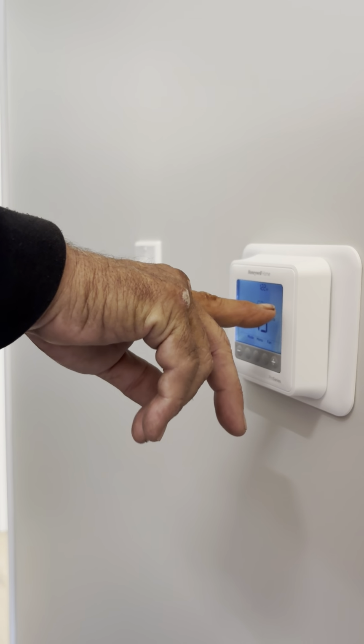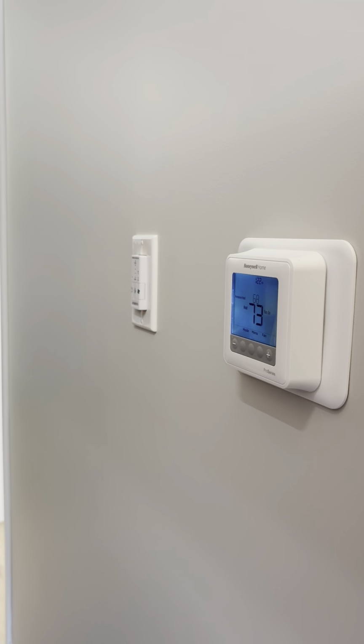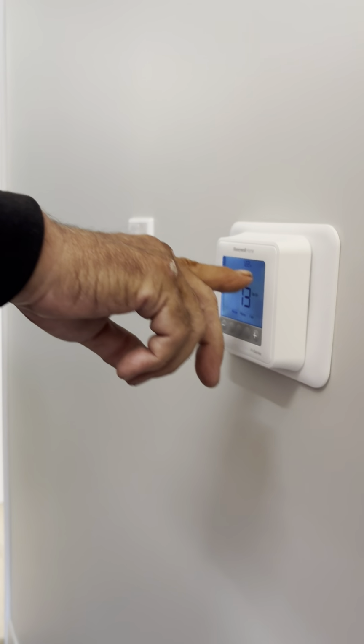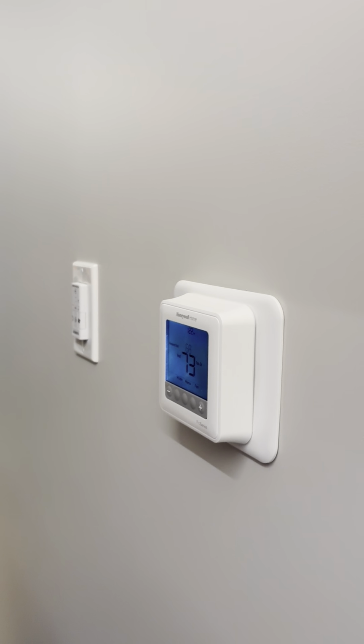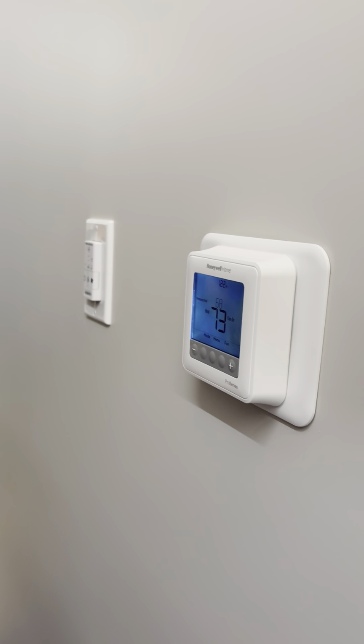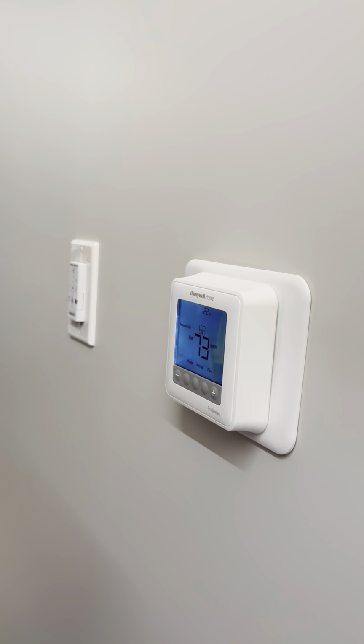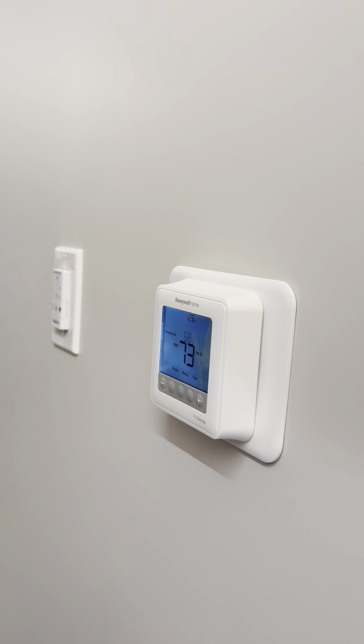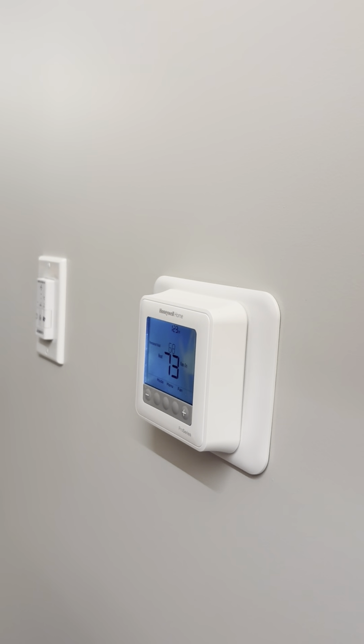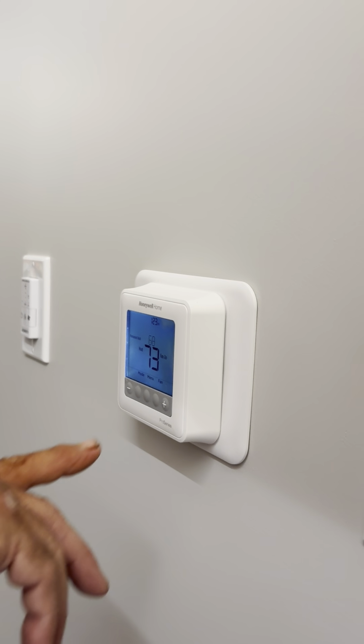Once it's flashing, like it is right now in the corner, it just turned off. There's a 5-minute time delay, so when it kicks in, it'll keep flashing for 5 minutes before anything starts. Once the 5 minutes are up, the light will come on solid, showing it's in heating mode, if it was calling for heat, or cooling mode.